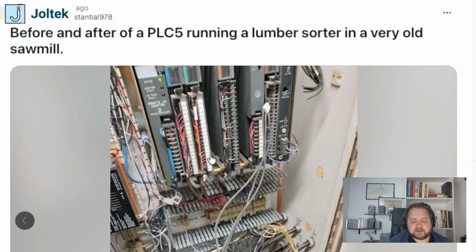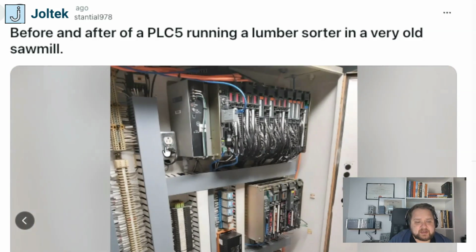So for me, it doesn't make a whole lot of sense to clean up the panel and spend all of those engineering and labor hours to basically revamp what's currently in there if we're not going to go ahead and ensure that there is no obsolescence risk for this specific business. And if we want to get down into those details, what does it take to take out a PLC5? Obviously, it depends a little bit on the system. Generally speaking, it is not extremely difficult to migrate.